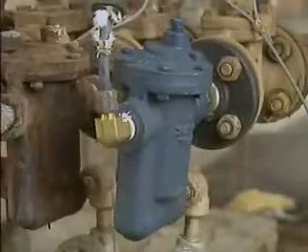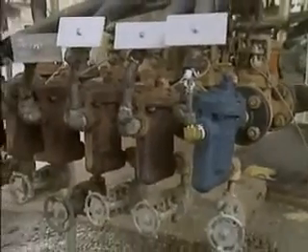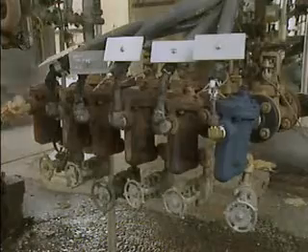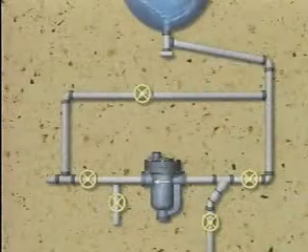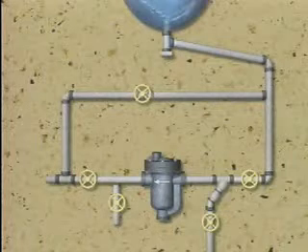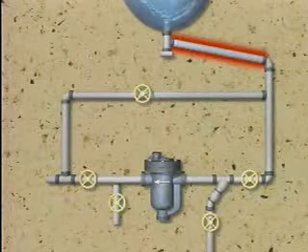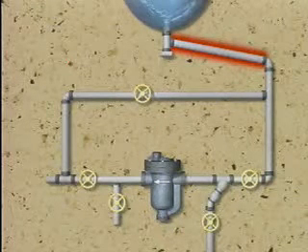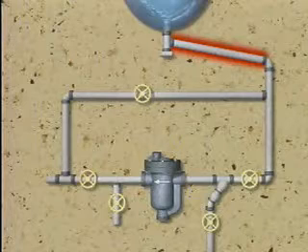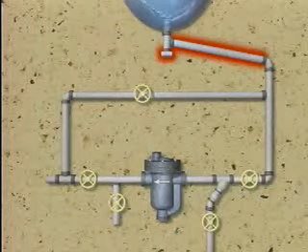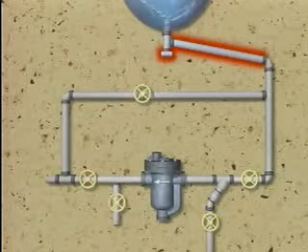A steam trap is usually an integral part of the steam trap station, which includes one or more steam traps as well as associated valves, piping, and related components. Multiple steam trap stations may be used to remove condensate from a facility's steam system. A drip line connects to the lowest point of the steam line or process equipment through which live steam moves. Condensate collects in the drip line, which also includes a dirt pocket to trap larger particles of dirt or scale that may be dislodged in the steam lines.